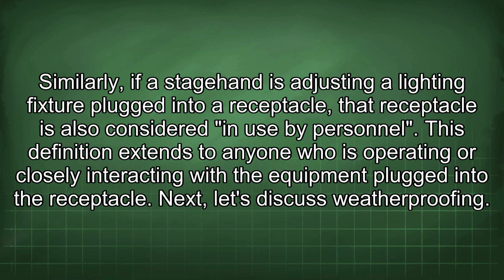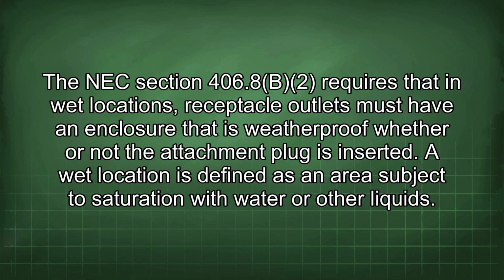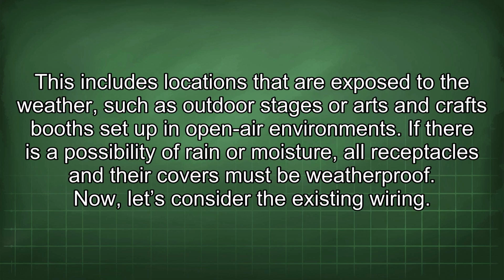Next, let's discuss weatherproofing. NEC section 406.8(B)(2) requires that in wet locations, receptacle outlets must have an enclosure that is weatherproof whether or not the attachment plug is inserted. A wet location is defined as an area subject to saturation with water or other liquids. This includes locations that are exposed to the weather, such as outdoor stages or arts and crafts booths set up in open-air environments. If there is a possibility of rain or moisture, all receptacles and their covers must be weatherproof.